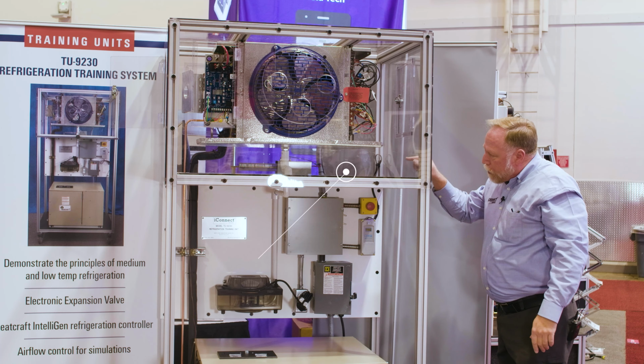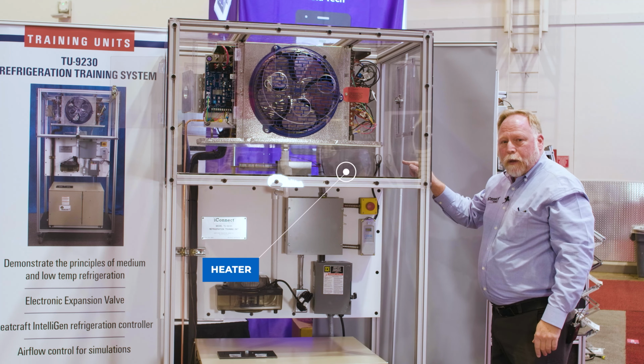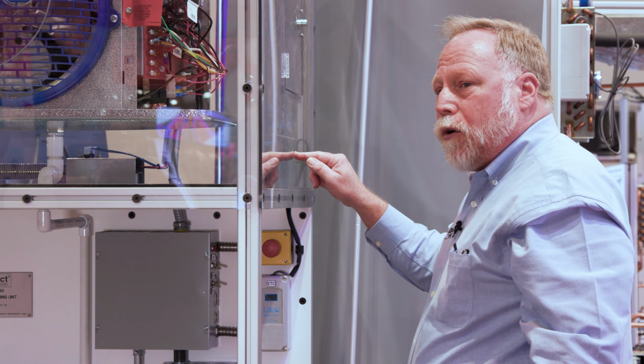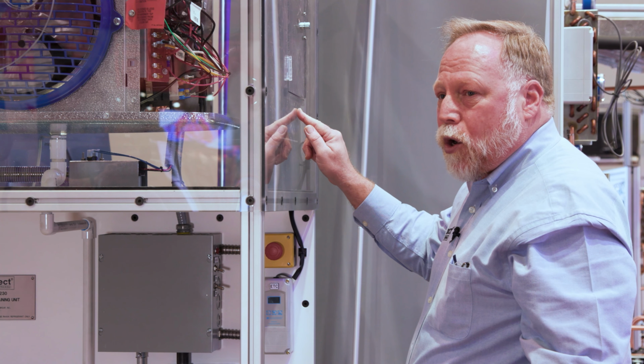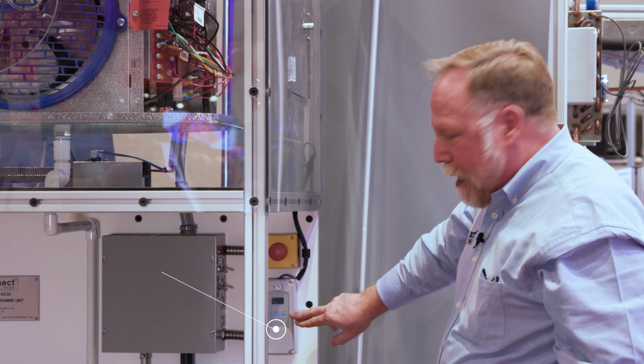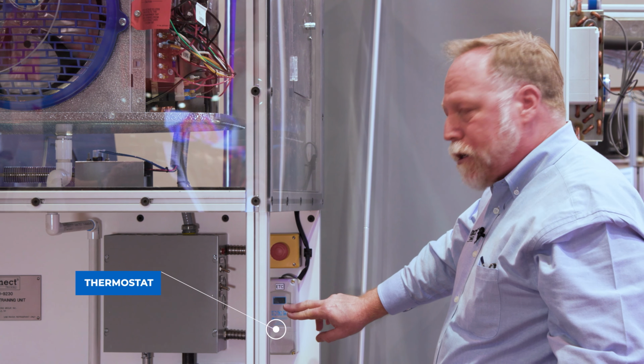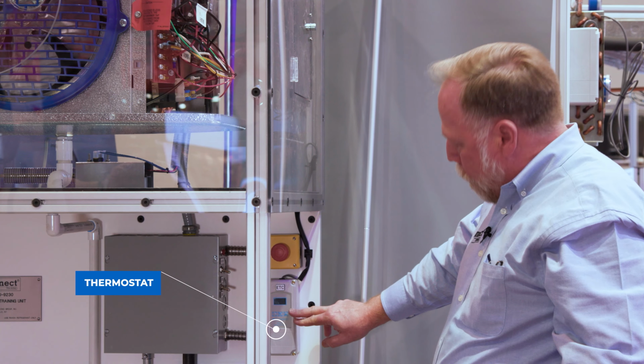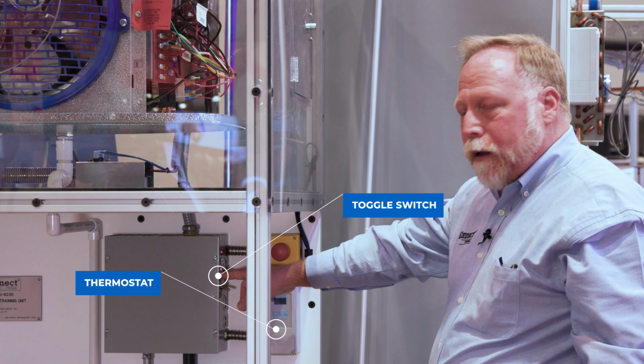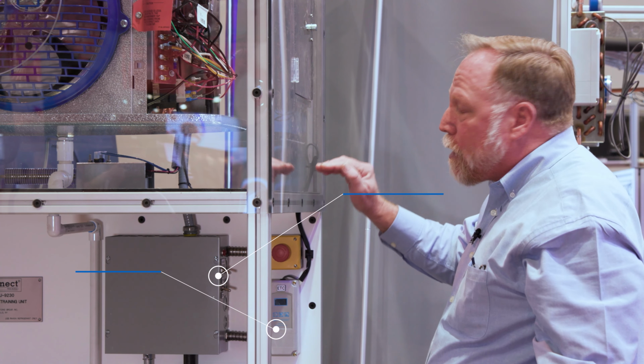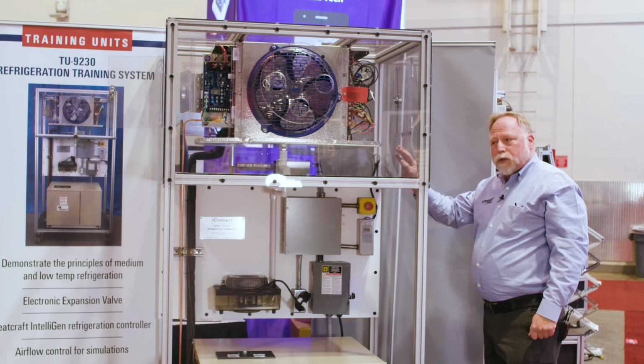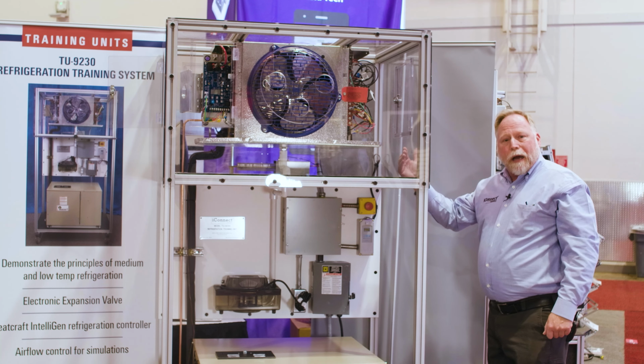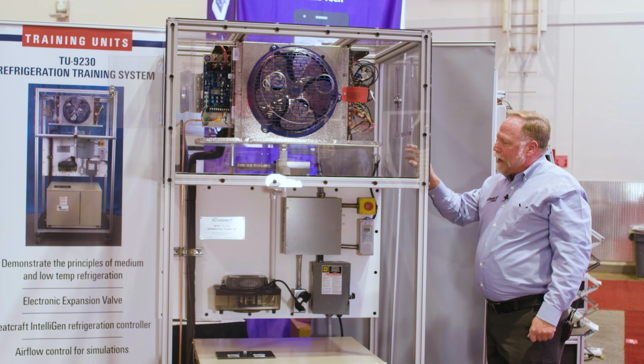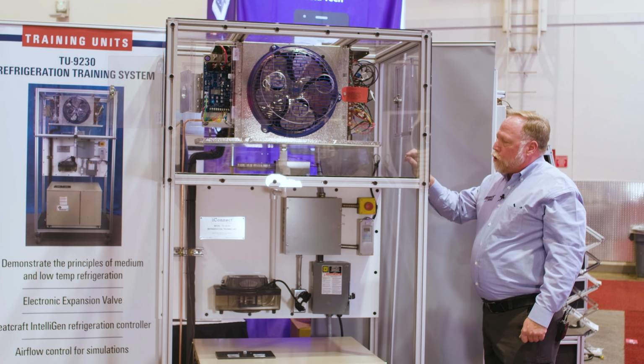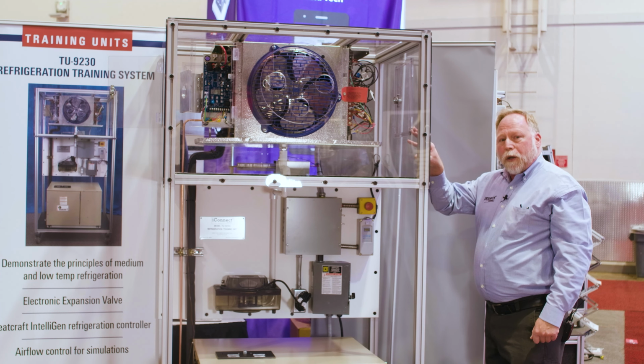If you look over here underneath the unit, we have a heater. We can adjust the load coming in on the back side of that coil with a thermostat down here. This thermostat controls the heater itself. We have a toggle switch over here, and you can adjust how much load you actually want to put on this coil. So you can simulate a hot pull down if you want to, giving you the ability to choose the environment this indoor coil is going to be working on.